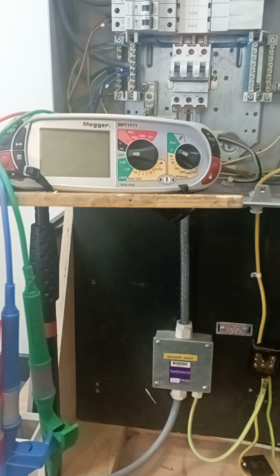Okay. Now that I've got that disconnected, one of the next checks is to take my wee wand, my non-contact voltage detector, and put it onto the incoming side of my main switch to prove that it's working. I'm then going to place it onto the conductor that I've just disconnected and the main earthing terminal. Remember, this part of the installation might be alive because currents are circulating here, or this conductor might be alive.